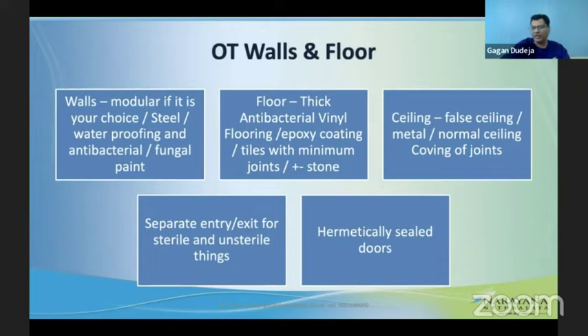For ceiling, a false ceiling works, but it's difficult to clean. A metal or powder-coated metal ceiling, or a steel ceiling, works fine. Whatever you do, make sure the joints are covered so there is no collection of dust in the joints where the wall meets the ceiling.